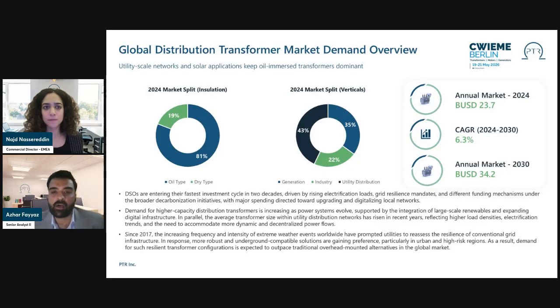Another trend we have observed in the recent past is a clear increase in the average size of distribution transformers within utility networks. Why is that? Because load density is increasing. Urbanization, electrification of heating, and EV adoption all require higher capacity distribution units than in the past.